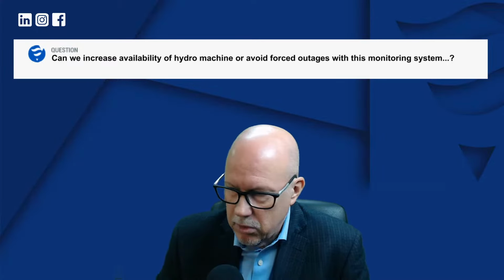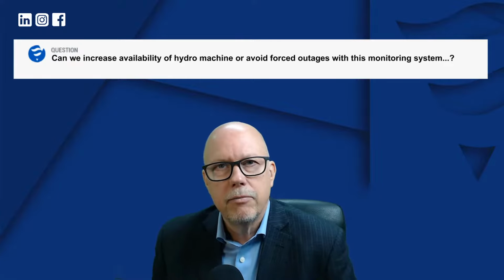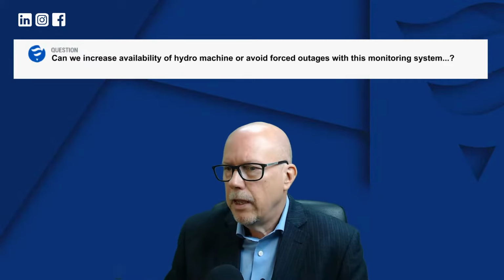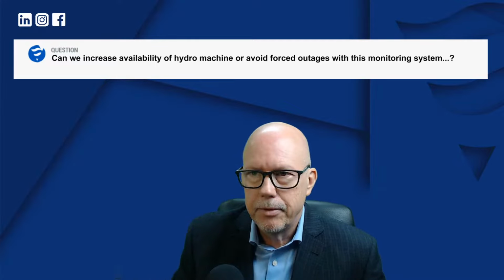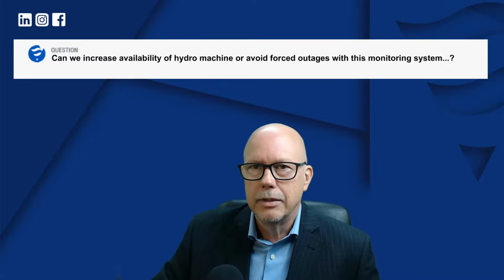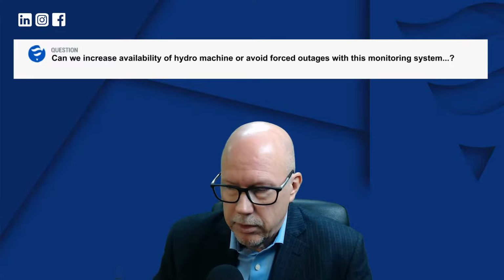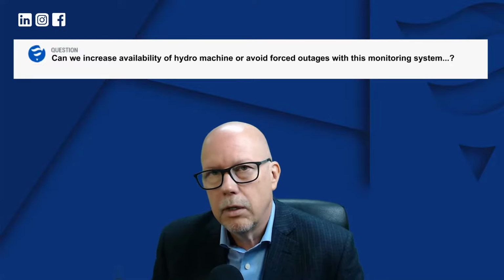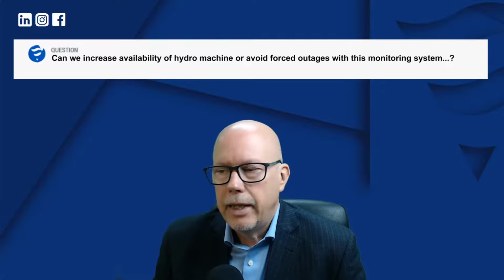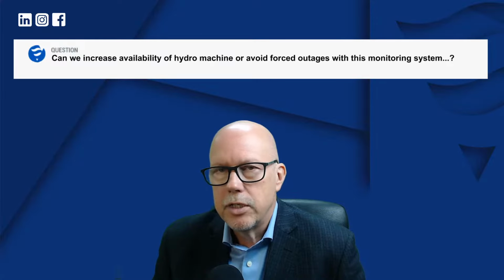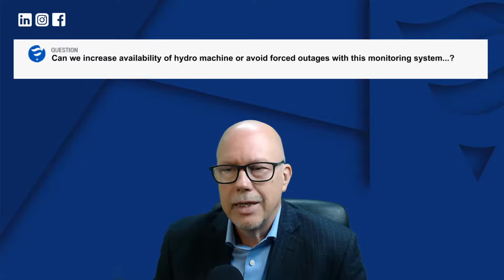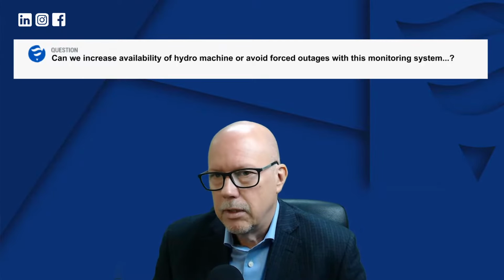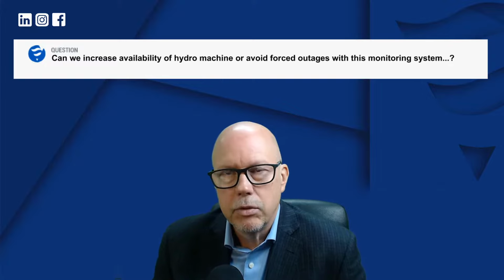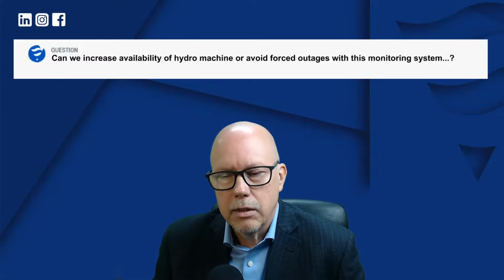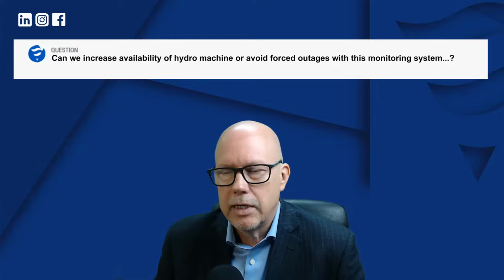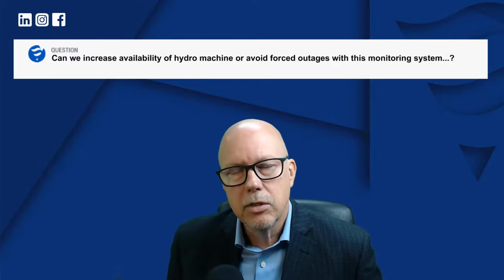One of the best examples that I know of is power stations that have multiple units. There's a maintenance plan, so unit 1 is stopped in January, unit number 2 is stopped in July, and so forth. And I've actually witnessed a case in the States where they stopped the unit for maintenance, and while they were doing that, an adjacent unit had a major failure. So now they had 2 units that were down. The information that a system like this can give you allows you to make decisions or make assessments. Whereas, well, we have 4 units. Unit 3 is next in line to be stopped.